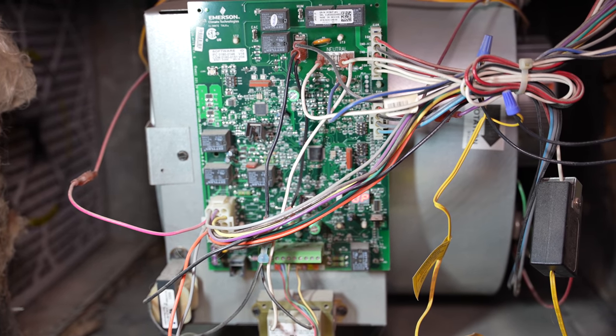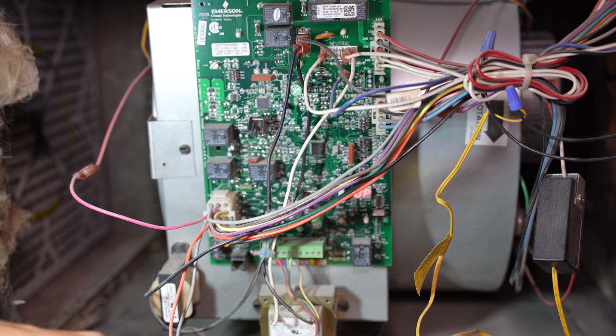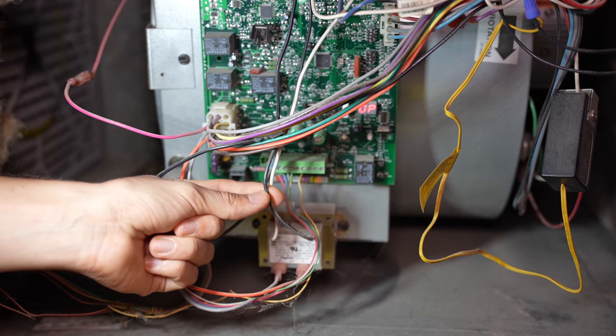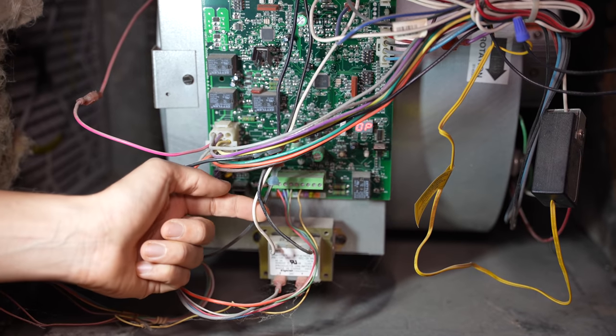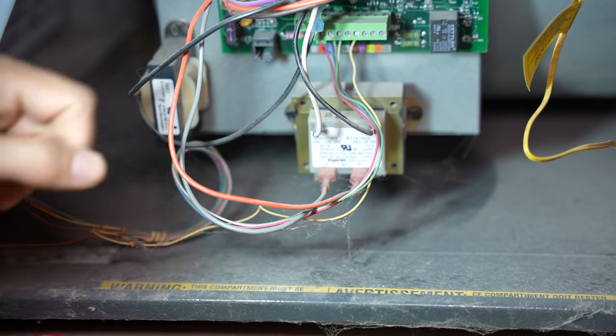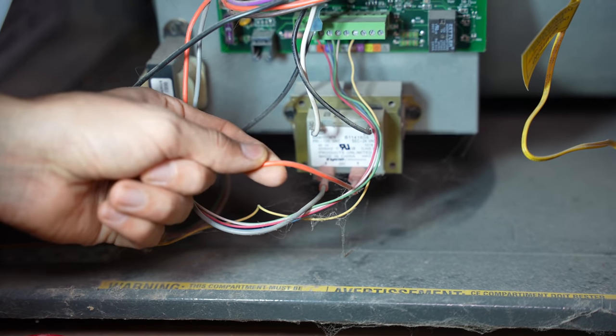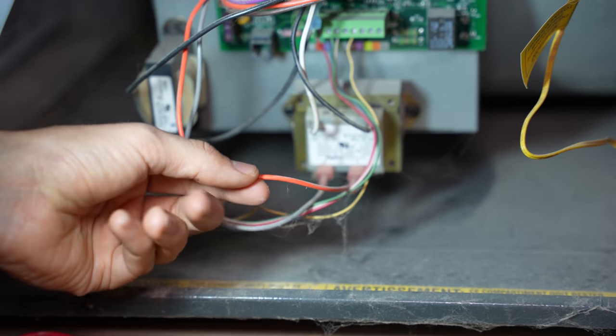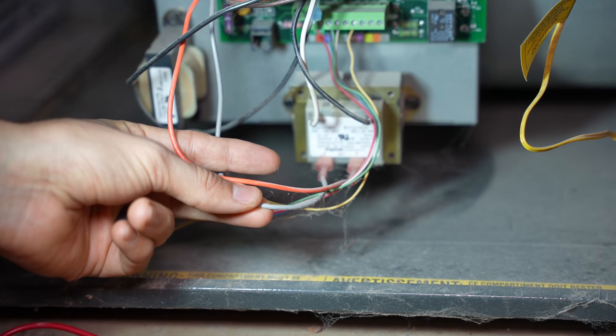In most cases, the easiest way to find the 24 volt common is to go right off of the transformer. Usually, the black and the white wires, that's going to be the 120 volts. Black being the hot, and the white being the common, or the neutral. And on the 24 volt side of the transformer, you have a red and a gray. Usually the red is going to be our hot wire, and then the gray is going to be the common.